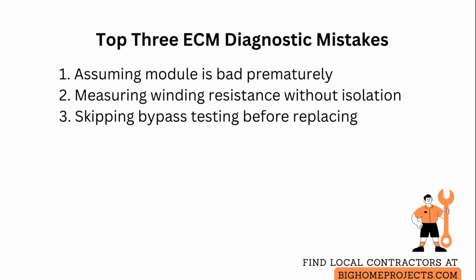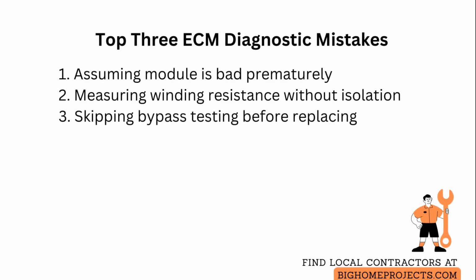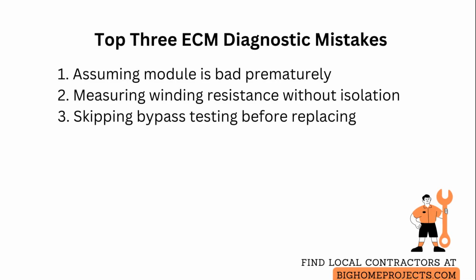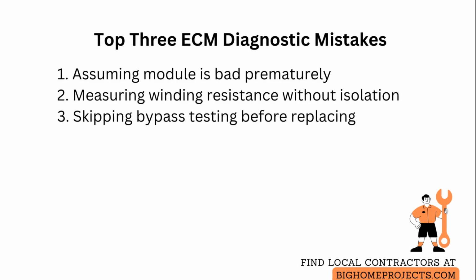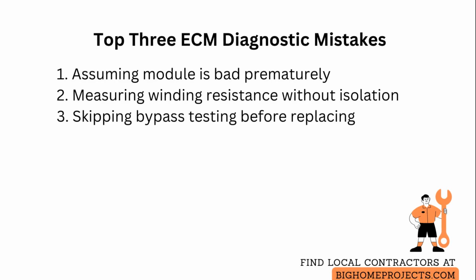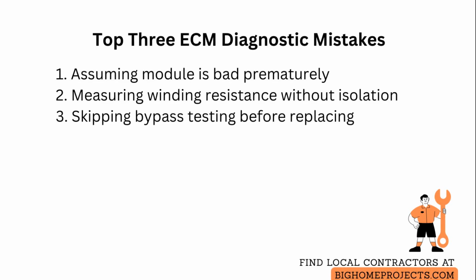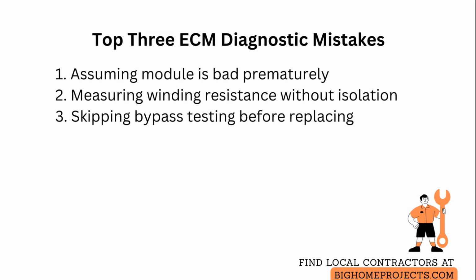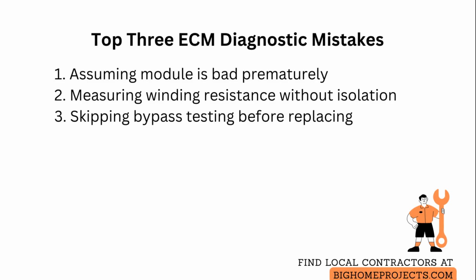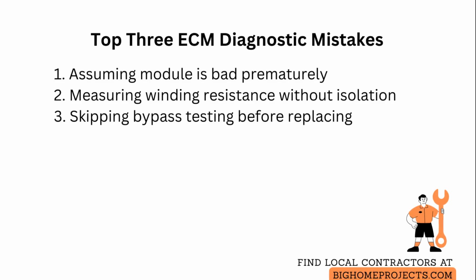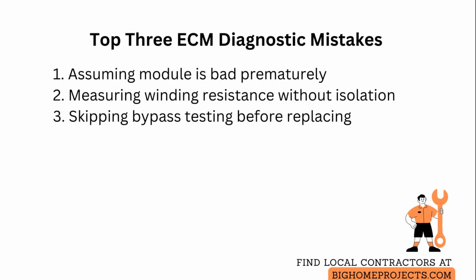Common mistakes include assuming the module is bad without confirming voltage supplies and control signals, which leads to unnecessary parts replacement. Always measure both the high voltage feed and the specific low voltage control level before ordering parts. Another frequent issue is misinterpreting winding resistance numbers because test leads are not isolated from the system. Disconnect motor leads from the module before measuring to avoid false readings.